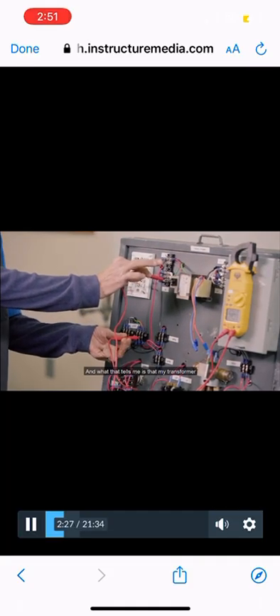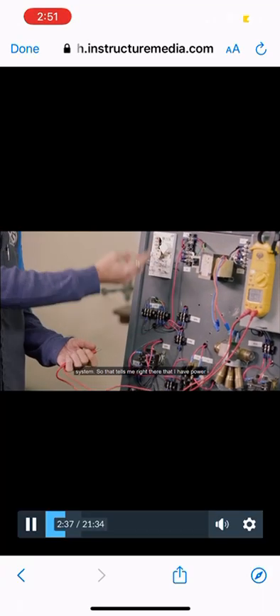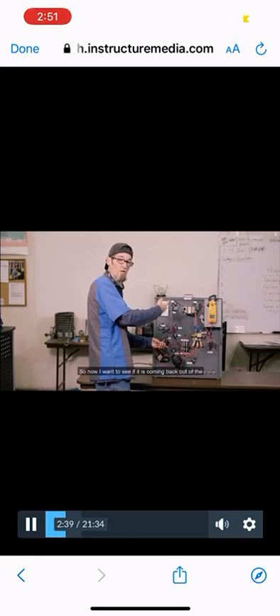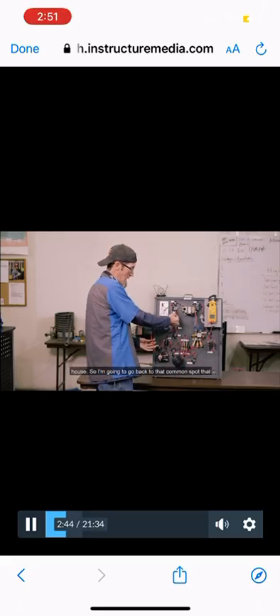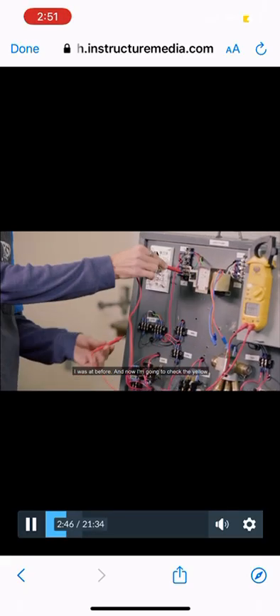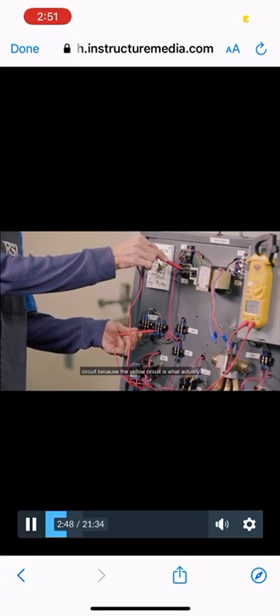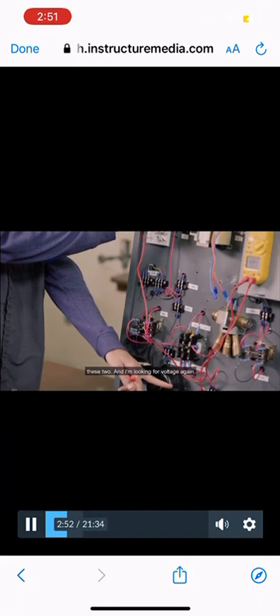And what that tells me is that my transformer right here, the thing that takes our high voltage coming into the unit at our disconnect and converts it down to a lower voltage for our control system, is working. So that tells me right there that I have power going to the house. So now I want to see if it is coming back out of the house. So I'm going to go back to that common spot that I was at before. And now I'm going to check the yellow circuit, because the yellow circuit is what actually takes care of this contactor down here, which turns on these two.